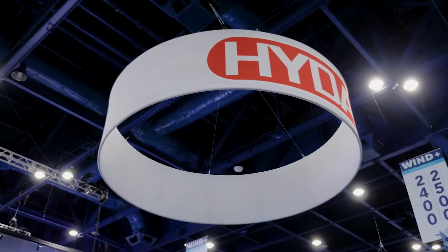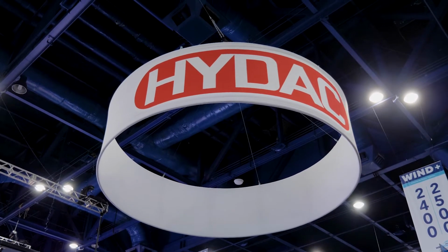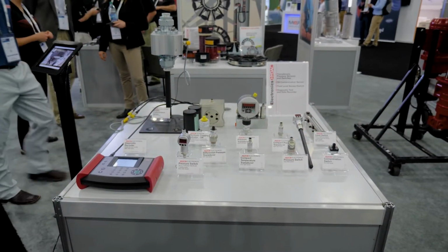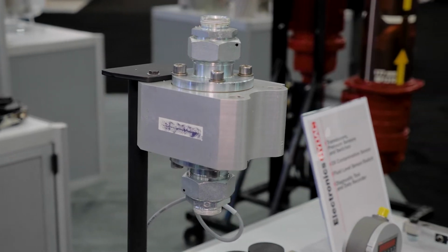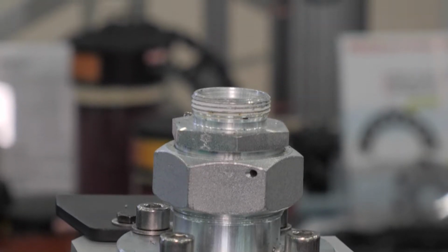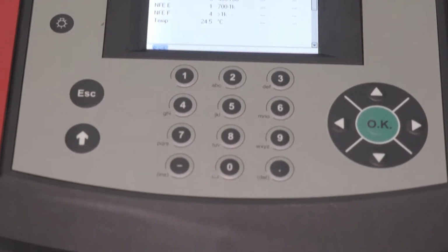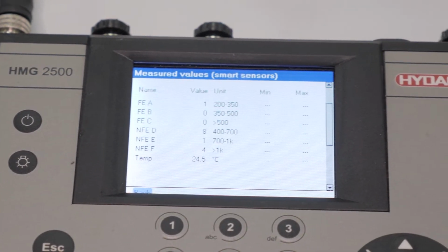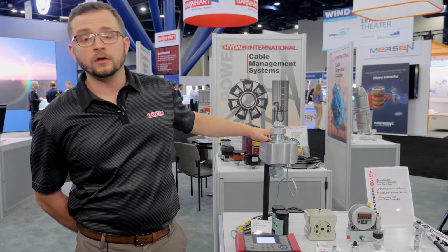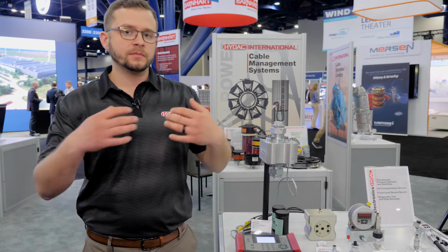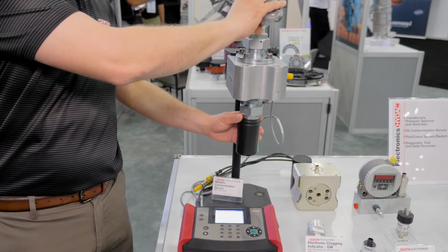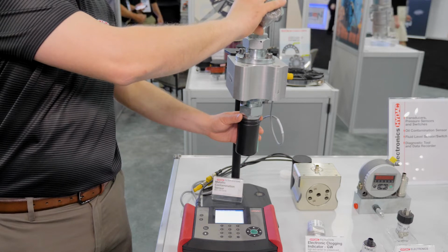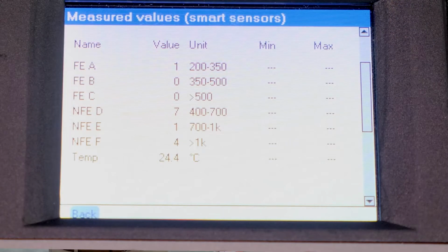We thought it was appropriate to bring our MCS 1000 series metallic contamination sensor as a product exhibit for its benefits to understanding the metallic particulate contamination in lubrication systems, specifically for gearbox lubrication systems. It's an inductive based technology and it measures non-ferrous and ferrous particulates. And the idea behind that is with that information, it's possible to provide a more predictive, better estimate of where the occurrence of increased particulate contamination is within a gearbox lubrication system.